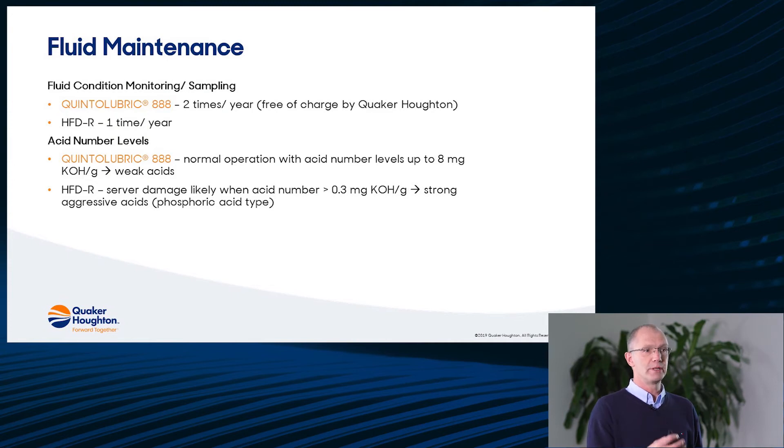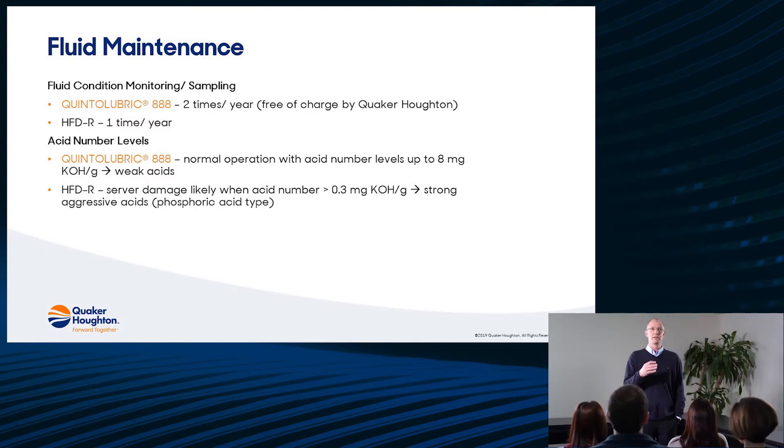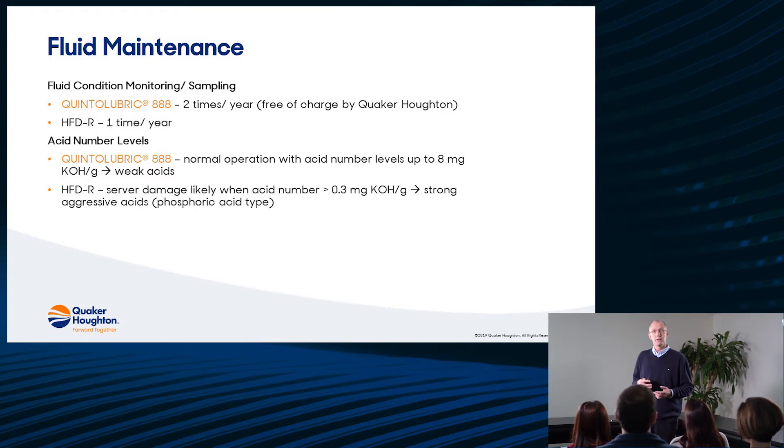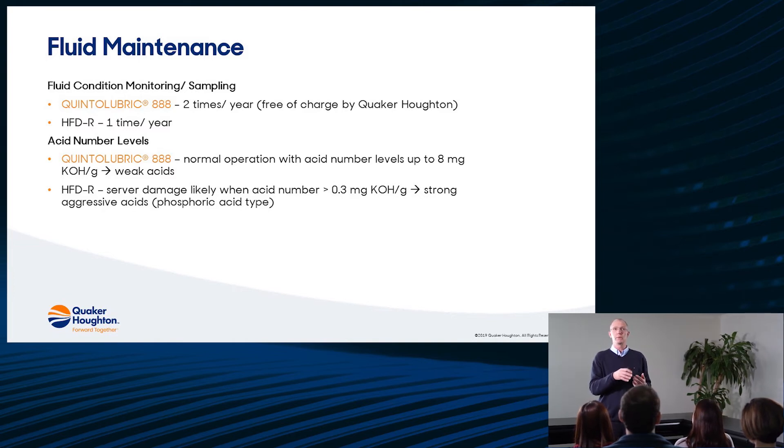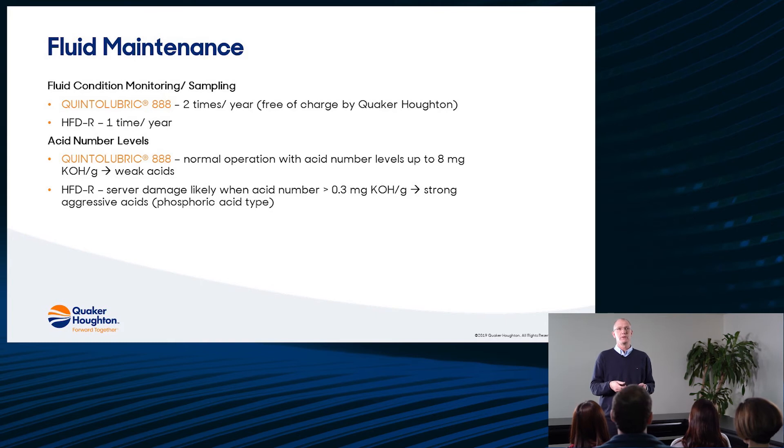Talking a bit more about the fluid maintenance: the main point is the acidity that is formed. With phosphate esters, the acids are very aggressive, so you have to take a sample regularly — once per year — to make sure that the acids formed are well controlled. With Quintolubric 888 polyol esters, the aging products are relatively weak acids. You don't have to take them out and you only need a sample two times per year.